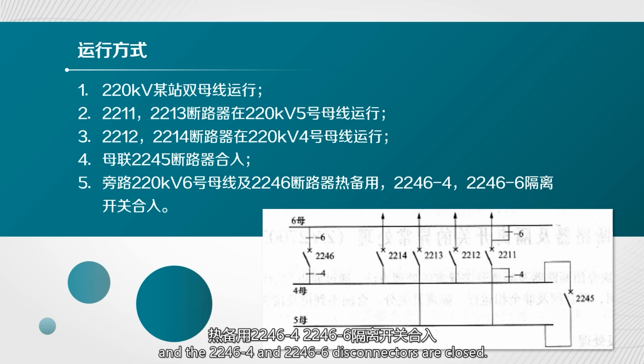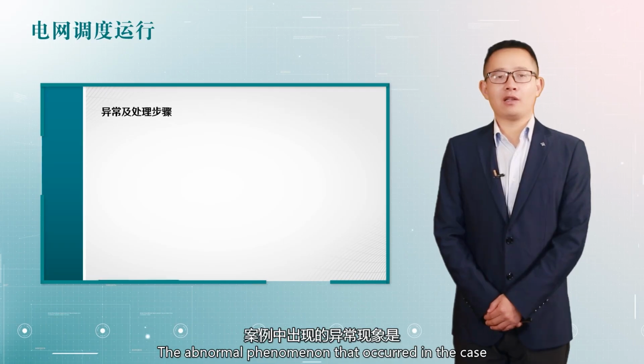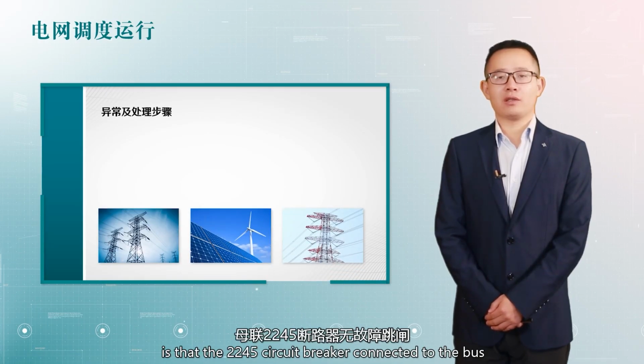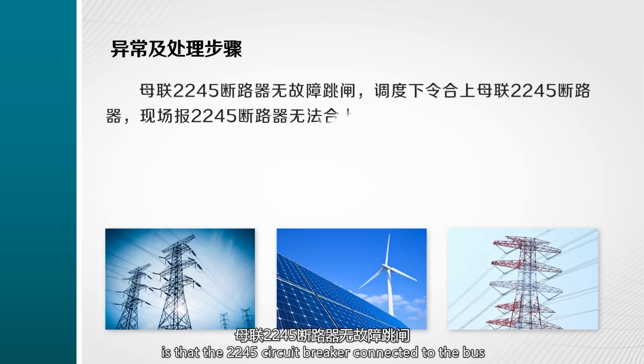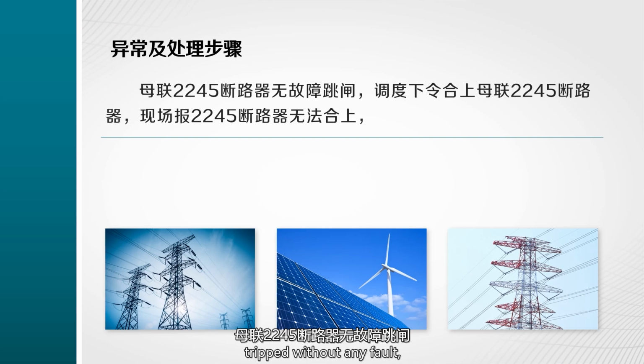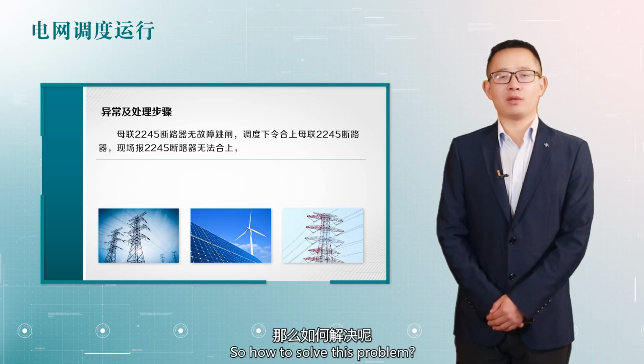and the 2246-4 and 2246-6 disconnectors are closed. The abnormal phenomenon that occurred in the case is that the 2245 circuit breaker connected to the bus tripped without any fault, and the dispatcher ordered the bus 2245 circuit breaker to be closed. On site, it is reported that the 2245 circuit breaker could not be closed. So how to solve this problem?